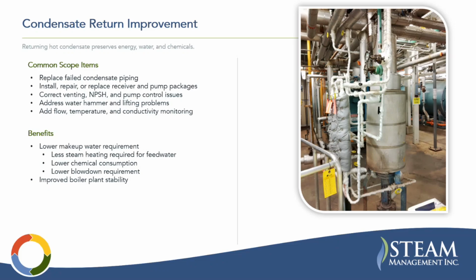But makeup water is where impurities are introduced to the system, and so the more makeup water you have, the more blowdown you have required, which is a waste, and we'll talk about that in a minute. You're also going to just generally improve your boiler plant stability.